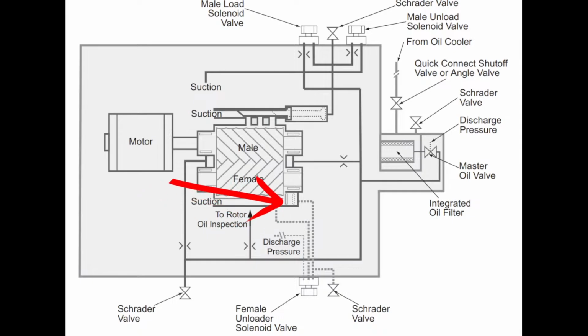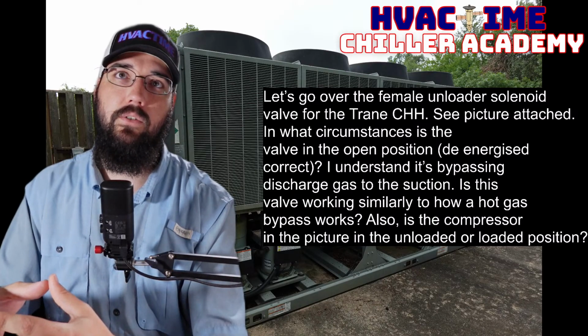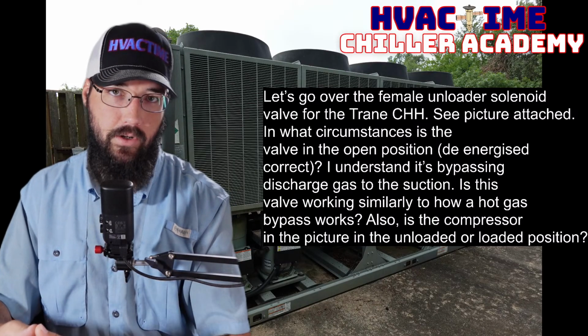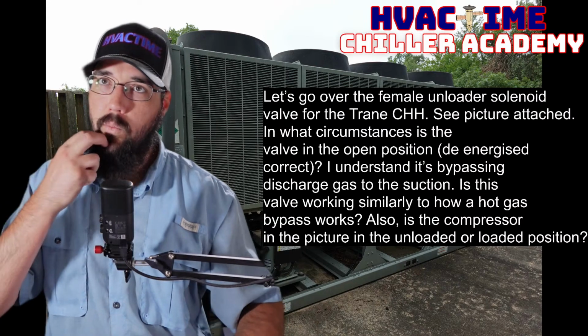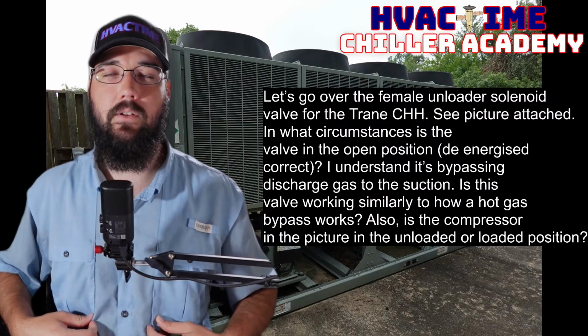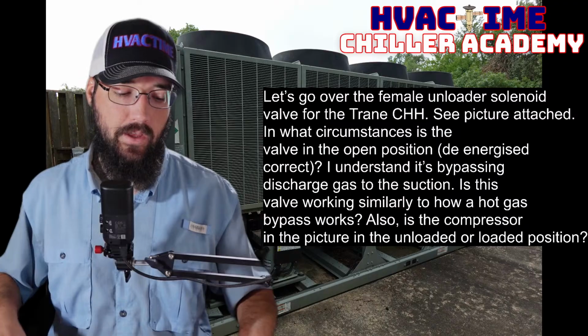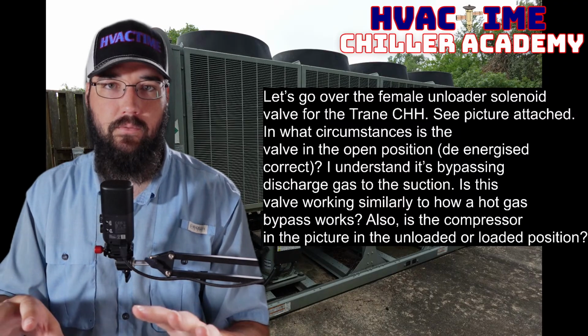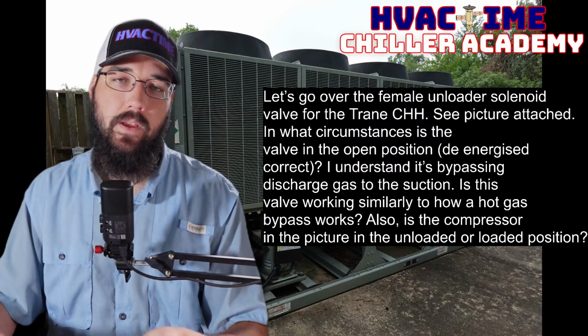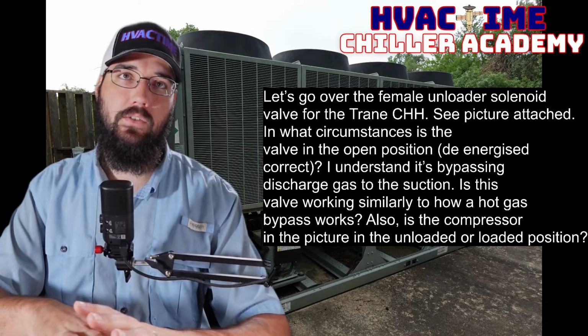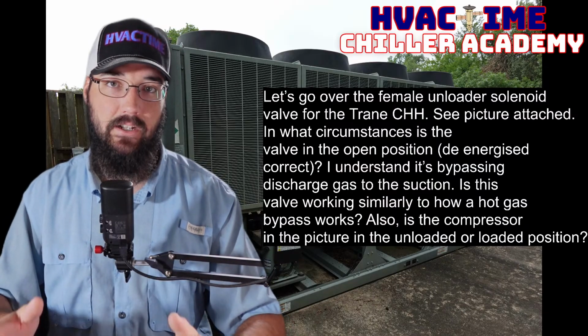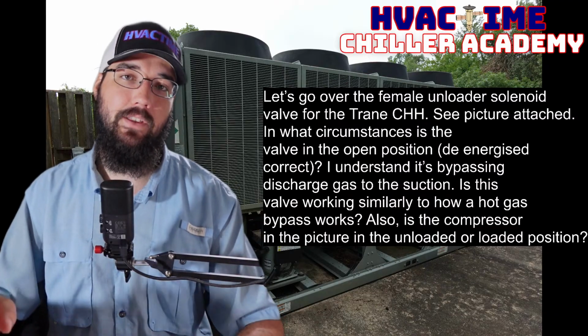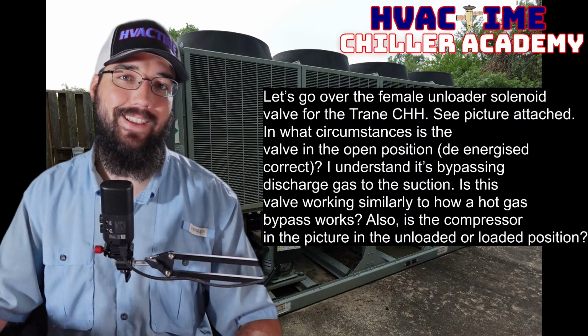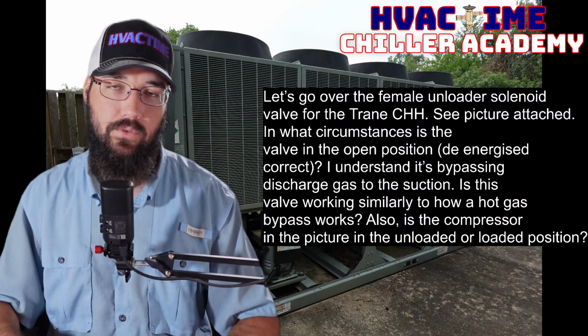So coming back to the female unloader, it's at startup that we need it. And one of the symptoms of this failing is we will constantly go into a low suction pressure alarm. And this is where it gets real tricky. This has gotten me a lot of times. These chillers will pump down when they go to turn on. So when they start up, the evaporator is pumped down because they're using a DX style evaporator. So a DX style evaporator means that's direct expansion. Our refrigerant is inside of the tubes. Water is on the outside of the tubes.